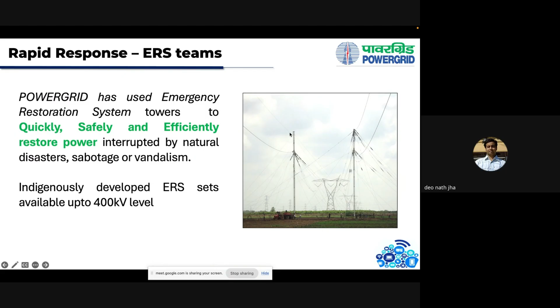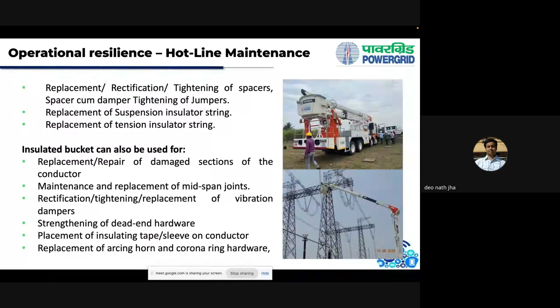Then the hotline maintenance systems. These are insulated bucket trucks. The person goes inside the bucket, and with the lifting of the boom, reaches up to the charged conductors or charged assets being used. This is done for replacement, rectification, tightening of spacers, spacer damper systems in a transmission line, and also to repair various assets in the substation. This allows the person to repair or restore assets without taking any outage or shutdown of the equipment.